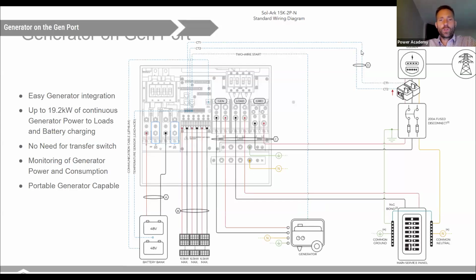So the Sol-Ark 15K has dual battery inputs on the left. The generator port, you can bring in up to 19.2 kilowatts of continuous AC power. Now that could be a generator with 2-wire start enabled. It could be AC coupled solar. So if you've already got maybe 15 kilowatts of AC coupled solar on the roof, just bring that in through the gen port. If you still want a generator and you have AC coupled solar, we can utilize a transfer switch and bring the generator in through the utility port. And don't worry, the Sol-Ark 15K is smart enough not to backfeed the generator. So if you do put that generator on a transfer switch and you've got AC coupled solar and you're worried about backfeeding it, the Sol-Ark 15K has got protections built in to realize when it's a generator providing power and prevent backfeeding the generator when you have that transfer switch installed.